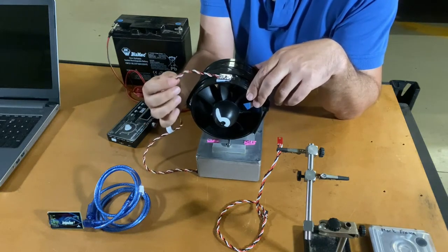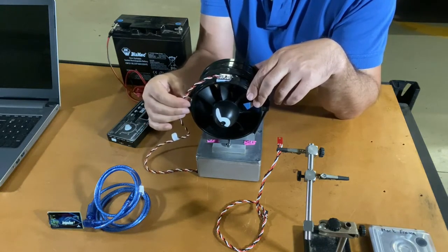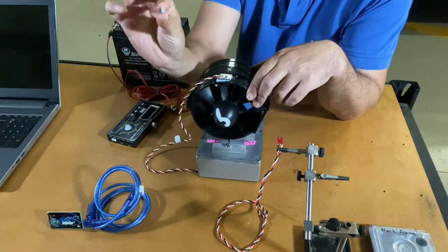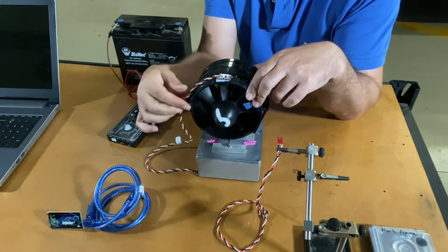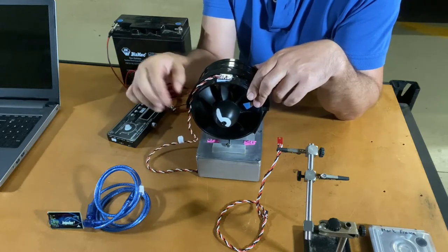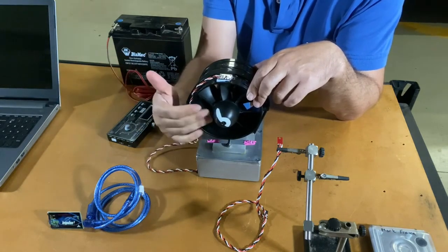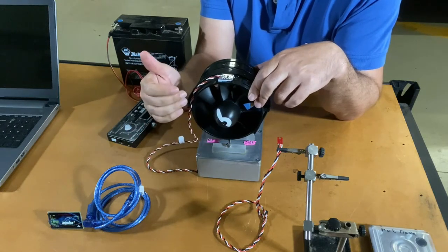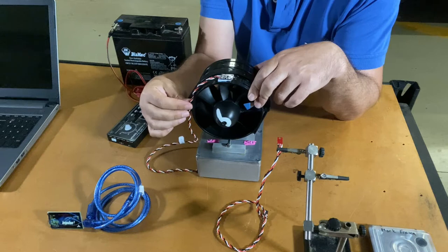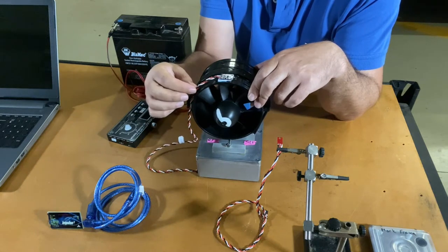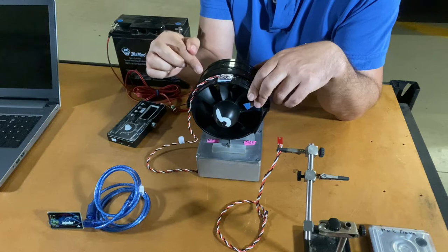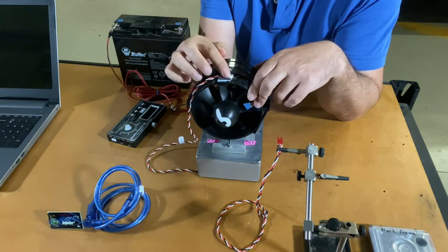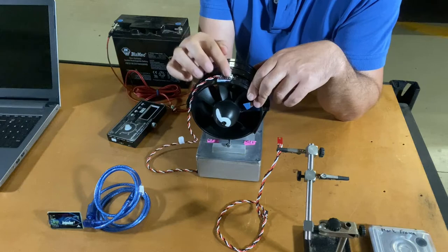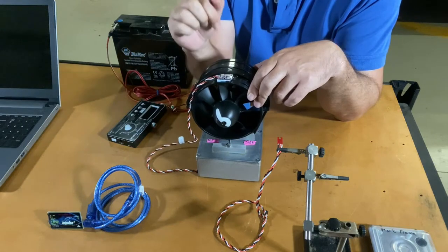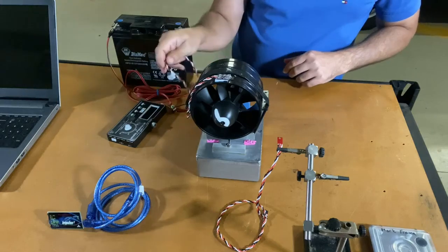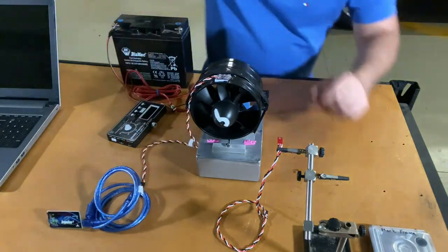It's a good idea to actually tie down loose leads. So what I tend to do is I use a bit of blue tack, which is there, mount it to the side, and tie all the leads down. For two reasons. You don't want the lead to fly inside the impeller, which is a hazard there. You want to tie all that up. And the second reason is that the vibration of the lead onto the case of the impeller could also jeopardize the true vibration or imbalance measured by the accelerometer. So that's installing the accelerometer onto the EDF.